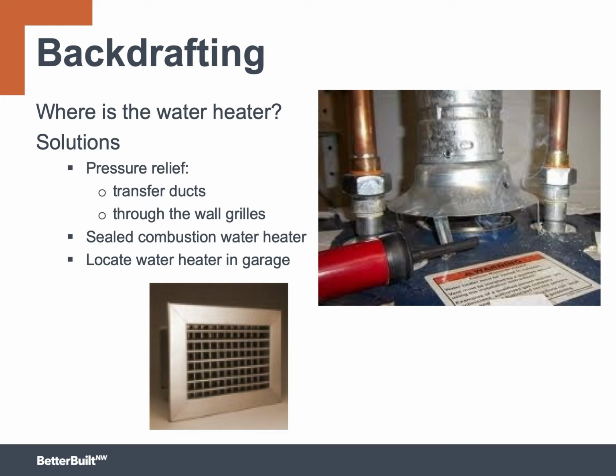Air leaks in the furnace cabinet and the attached ductwork could cause some naturally aspirated water heaters to spill flue gases into the space. So if you're using a naturally aspirated water heater with a B-vent, you'll definitely want to make sure that it's got adequate combustion air. Of course, the best solution is just to buy a sealed combustion water heater if you're going to locate it anywhere inside the conditioned space. The other possibility is to locate the water heater in a different space than the furnace. The furnace would be in an insulated room and the water heater would be outside. In the past, it was fairly common to cut a hole to the outside, maybe have a short duct running to the crawl space or running to the outside. That clearly defeats the purpose of building a tight, energy-efficient house and putting the ducts inside. Check with local code officials to be sure that your solution is going to pass muster.